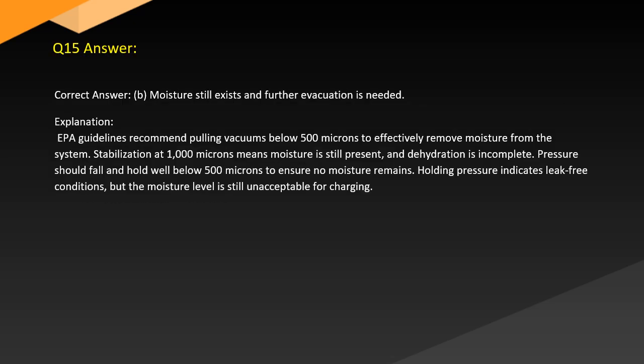Answer. Correct answer. B. Moisture still exists and further evacuation is needed. Explanation. EPA guidelines recommend pulling vacuums below 500 microns to effectively remove moisture from the system. Stabilization at 1000 microns means moisture is still present and dehydration is incomplete. Pressure should fall and hold well below 500 microns to ensure no moisture remains. Holding pressure indicates leak-free conditions. The moisture level is still unacceptable for charging.